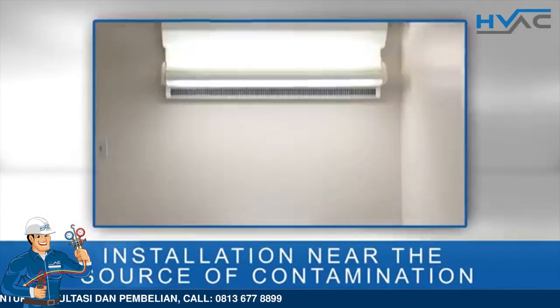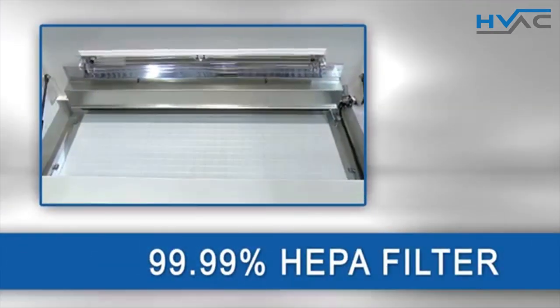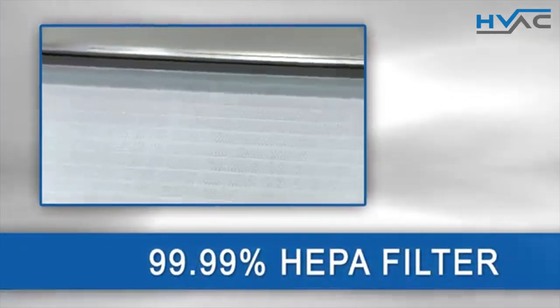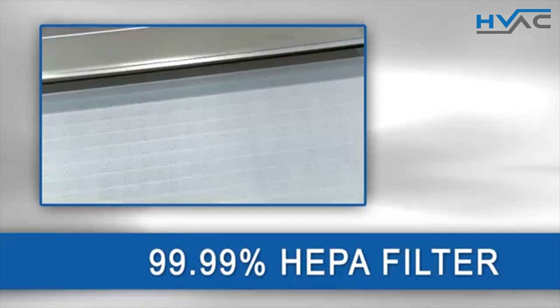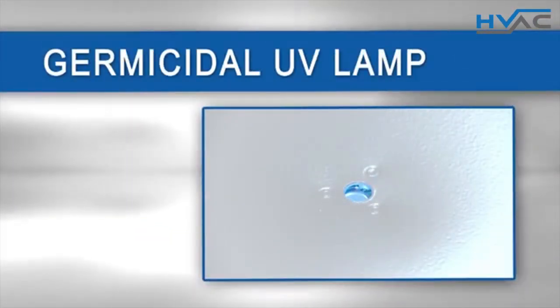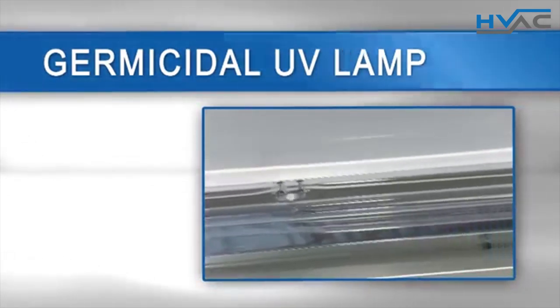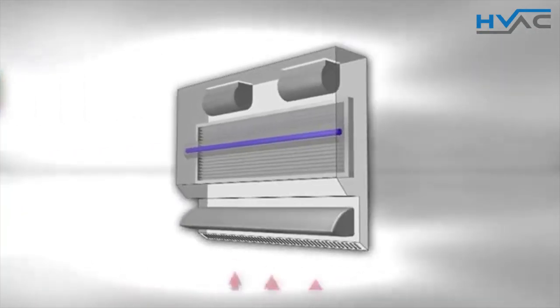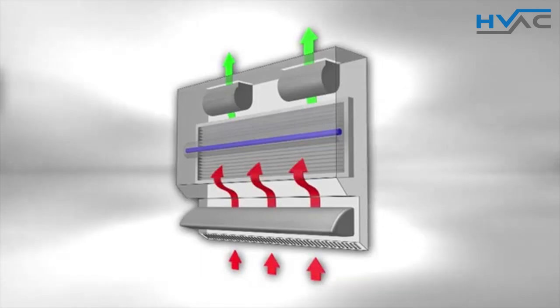The HEPA net will capture air at the source of airborne contaminated particulates above the patient's head, filtering contaminants with a 99.99% HEPA filter. The surface of the HEPA filter is radiated continuously by a germicidal UV lamp in order to prevent the growth of bacteria and viruses.